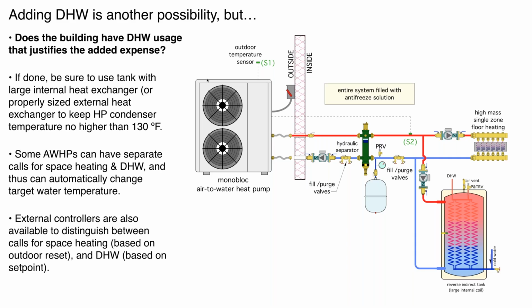And I put down, yes, this is a possibility, but you want to evaluate the domestic water needs in the facility. What we have found in many of these garage facilities is that there really isn't much demand for domestic hot water. They aren't really washing the equipment inside with hot water. Some of them might have a shower, others no shower, just a couple lavatories. When you have minimal need for domestic hot water, this may not be cost effective, as opposed to either a tankless electric water heater or a small tank type water heater. So I'm showing it as a possibility, but evaluate, is there enough domestic hot water demand to justify the cost of doing this?